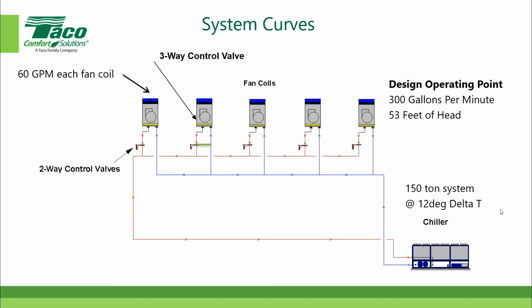We have 5 fan coils. Each one has a 2-way control valve, with the exception of one of the units, which has a 3-way control valve. This guy right here is a 3-way control valve to maintain minimum flow. With a 12-degree delta T, that means we need 2 GPM per ton. So if you multiply 150 tons times 2 GPM per ton, that comes out to 300 gallons per minute.